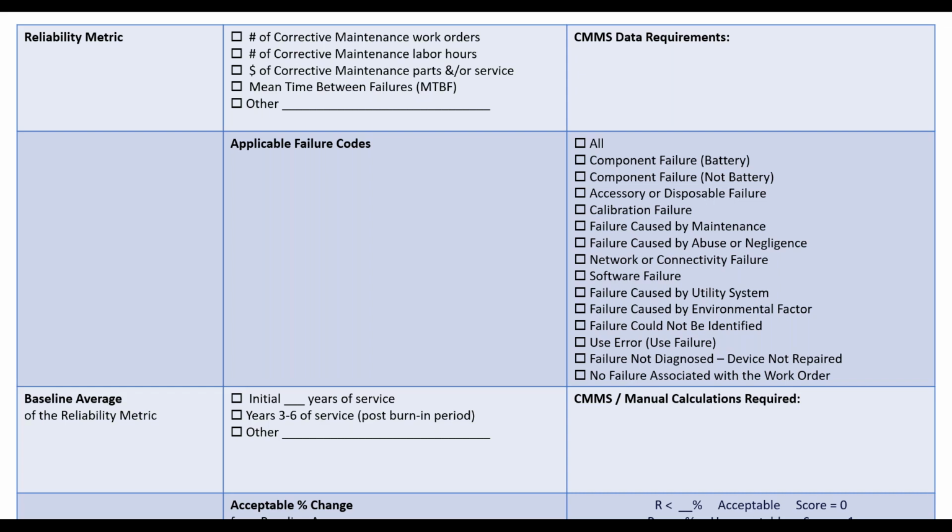Calibration failure is certainly one of the ones that really struck a chord with me, because if a pH probe or a pressure transducer calibration are not catching it throughout the year, and we're only doing it on an annual basis, that would be opening ourselves up to a great deal of risk during the year, as that transducer is changing over time. So decreasing the amount of planned maintenance and doing more cursory checks throughout the year will certainly reduce those numbers.